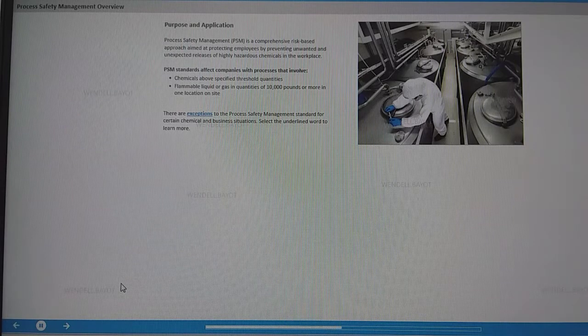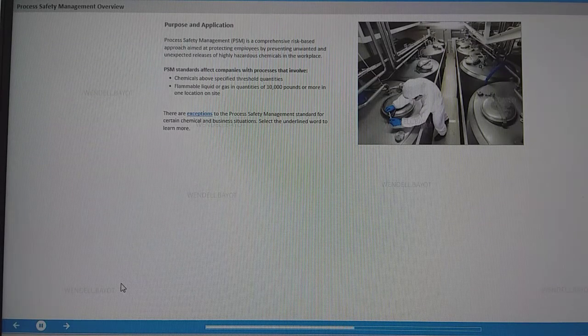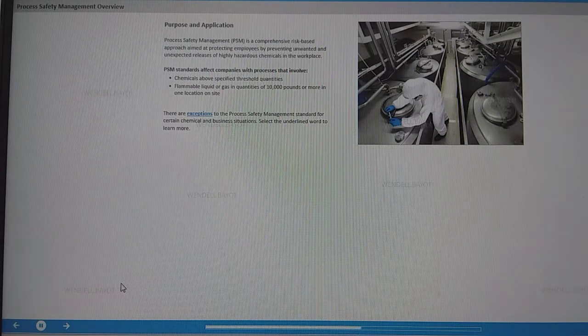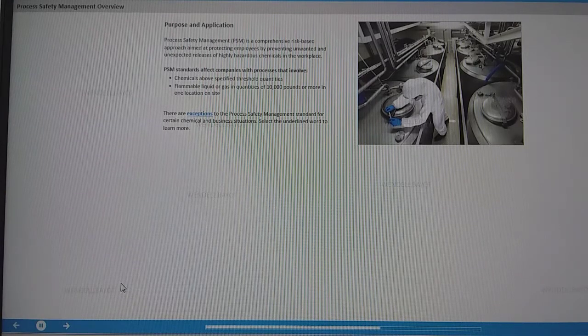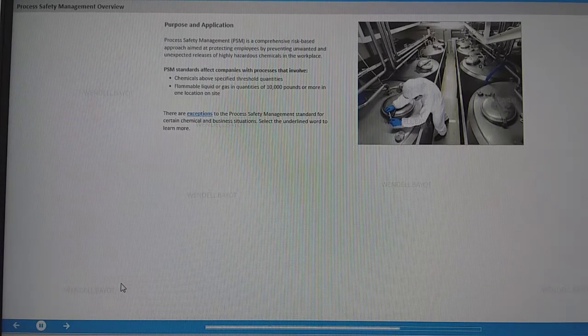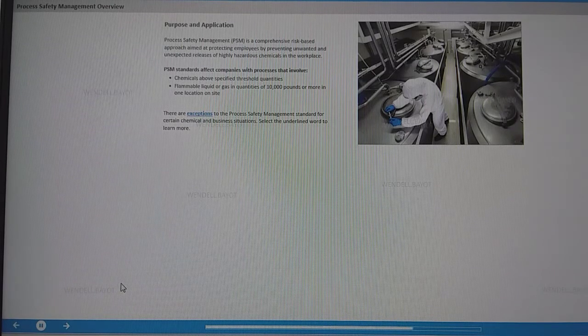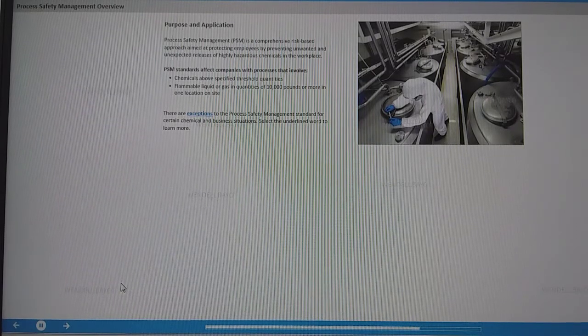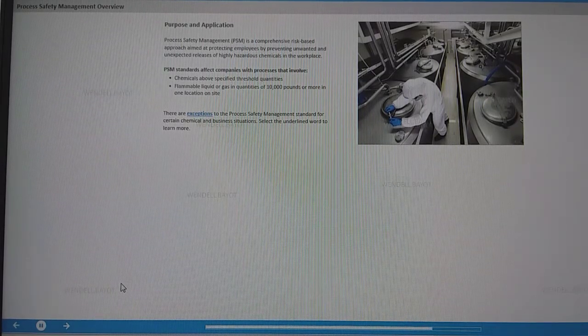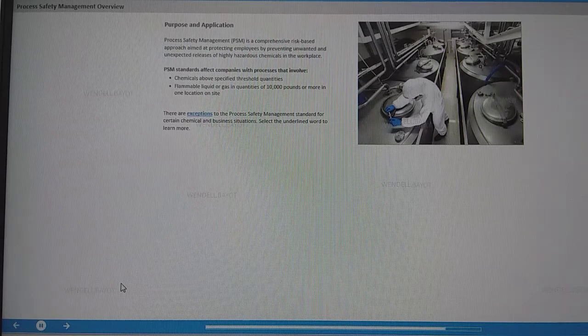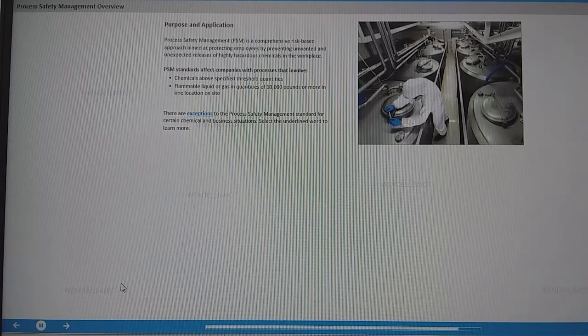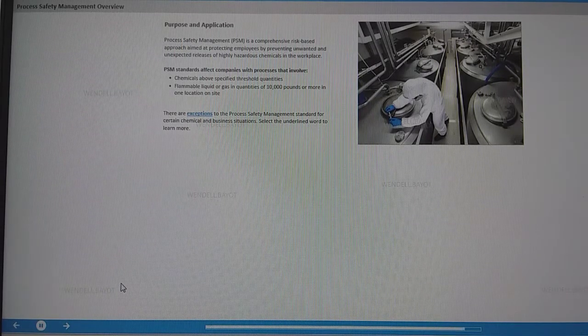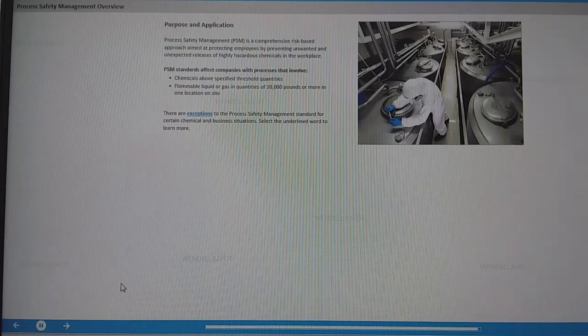In other words, quantities that have the potential for catastrophic consequences due to their explosive or toxic properties. And it also affects companies with flammable liquid or gas in quantities of 10,000 pounds or more in one location on site. There are exceptions to the PSM standard for certain chemical and business situations.